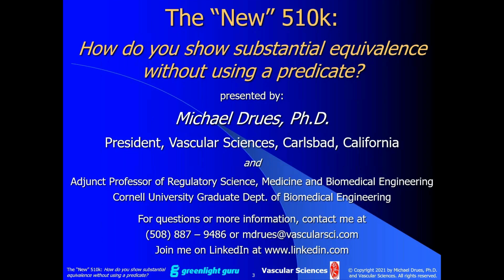However, if you were able to change the indication, in other words, if you could put a bare metal coronary stent in a coronary artery for some other reason, for example, maybe vasospasm, now at least it's theoretically possible that you could, via your risk mitigation strategy, lower your risk from class 3 PMA to class 2. And now doing that as a de novo or possibly as a 510K becomes a possibility.